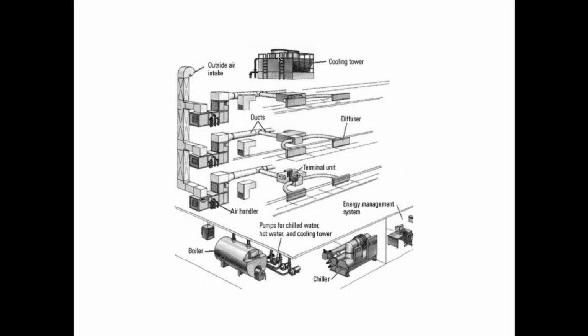You have to use chemicals to inhibit corrosion. You have to use chemicals to keep it from scaling up and rusting up and stuff like that. But especially you have an issue that you can get algae growing in there. And if you get algae growing in there, the algae can break off and clog up all these pumps and strainers and stuff that you have in this system, really mess things up, right? What else can you get growing in there? What temperatures did I mention to you? I mentioned something like 85 to 100 degrees. What bacteria loves that temperature?